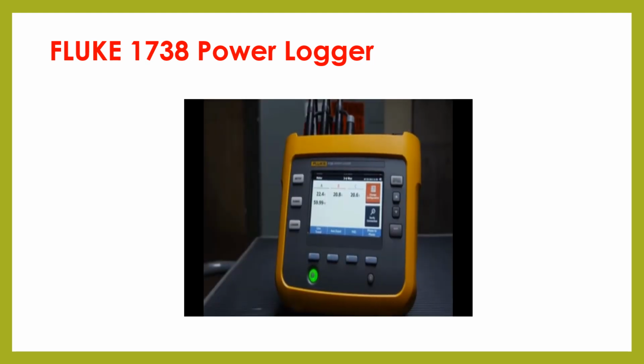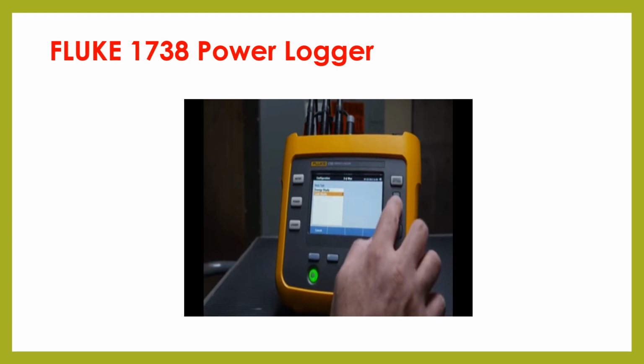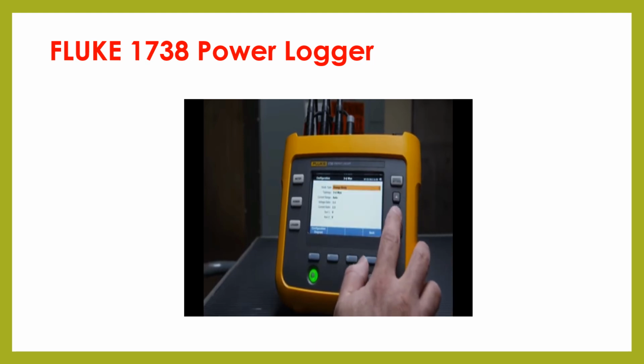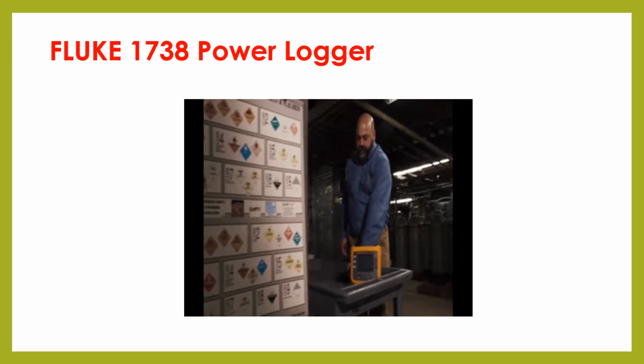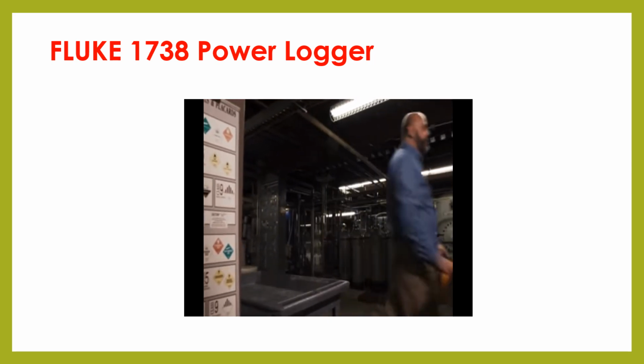To begin energy logging, start at the meter screen, select Change Configuration, and choose Energy Study under Study Type. Now choose Topology and select your circuit type from the list. Other settings, such as where the current and voltage transformers are installed, can be selected to ensure all measurements are shown correctly. Now it's time to install the 1730 at the load.